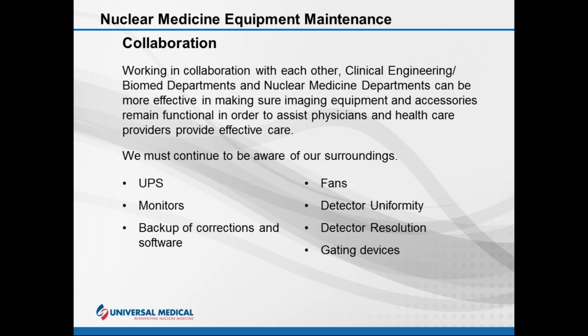Be aware of not just the camera, but the UPS and fans. If fans make noise, for instance, on a camera like a CardioMD or a C-cam, a small cardiac camera, there's a small little fan that provides air to what's called the EDC board. That board is really expensive. The fan goes, the board goes.